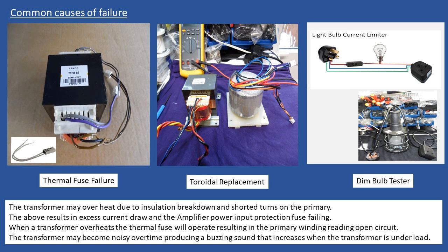The other point that I want to mention as well is sometimes you're not able to source a particular transformer. You can get the VA rating, but you can't match the voltage on the secondary. So let me take an example. Maybe you have a transformer that's failed, and the secondary voltage would be on a label on the side of the transformer, or you have to refer to the service manual or the schematic to determine what the secondary voltages are. But maybe it said it was 31.5 volts, and you're looking around, thinking, I can't source that. So what I can source is maybe a 36-0-36 and that'll be fine, is what you think.